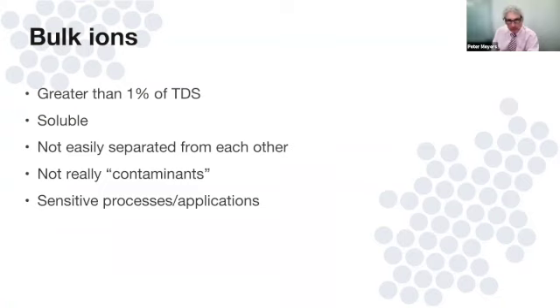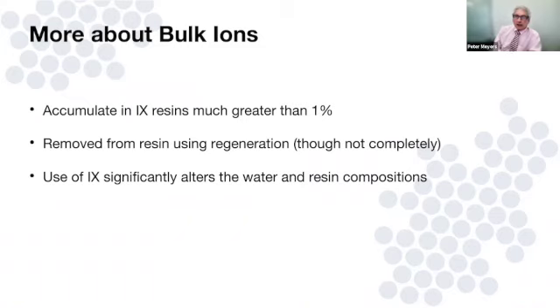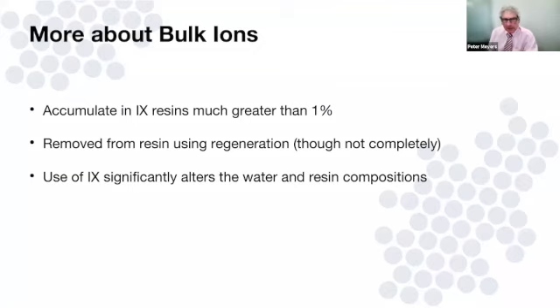On the anion side, the most common bulk ions are alkalinity/bicarbonates, chloride, sulfate, and nitrate. Silica is not on this list because silica is not ionized at neutral pH and therefore is not an ion. Even though these bulk ions aren't poisonous, we still need to remove them for sensitive processes like semiconductor manufacturing, boiler feed, and drinking water.